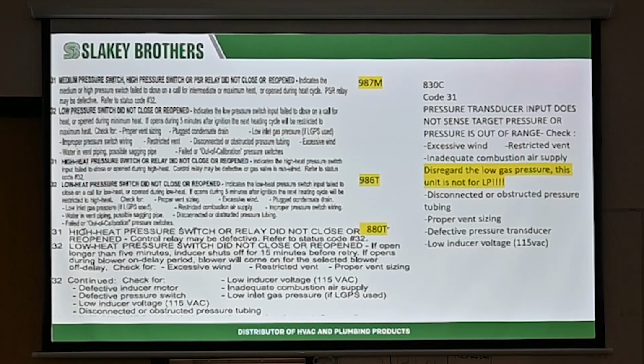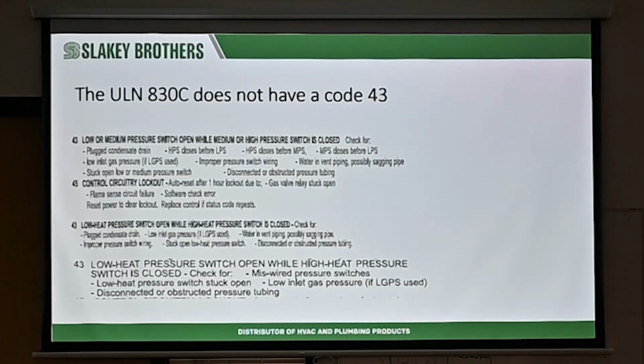Okay? And I don't want to go back to the picture, but the UEI, it's got the T. The little T is for this. This is reading pressure up here. So you're going to plug this into the T or just plug it into your meter. You can do it either way, depending on how you want to do it. If you want to have this try to run at the same time, either way you put your manometer in here, you turn on the unit, and you're looking for 0.68 plus 0.15 more. So I'm looking for at least negative 0.83 inches of water column or more. If I got, say, 1 point whatever inches of water column, and it stays steady, and I plug it in, and it still doesn't close the switch, it's a faulty switch.